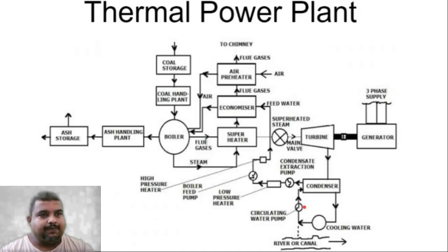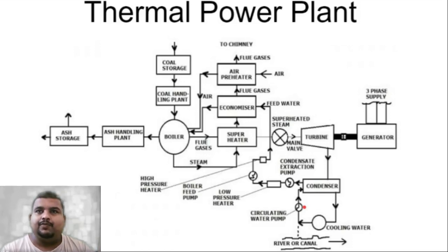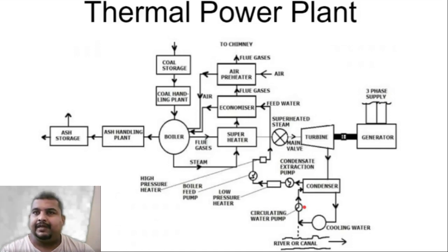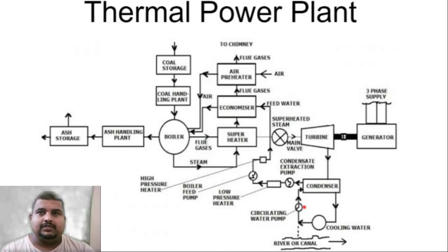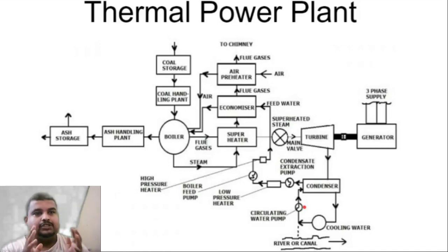The BFP — boiler feed water pump — increases the pressure of the boiler feed water considerably, to the highest pressure anywhere in the entire system. The highest pressure in the system is at the BFP outlet. From there, at high pressure, the water goes through the economizer — there is also an HP heater (high pressure heater) which further heats the water — and then through the economizer it is provided to the boiler. This entire path from condenser → CEP → LP heater → BFP → HP heater → economizer → boiler is called the feed water cycle.